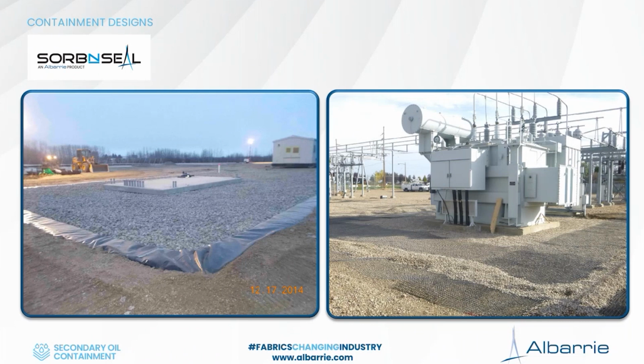I had a question. One of the applications we're looking at is 2 transformers next to each other. For that type of setup, is it typically one design for the whole thing, or usually separated? The IEEE guidelines basically call for, if you have 2 pieces of equipment fairly close together, the chances both fail at the same time are very small. So you can design one containment around multiple pieces of equipment and account for only the largest oil volume of the one piece within that containment area.